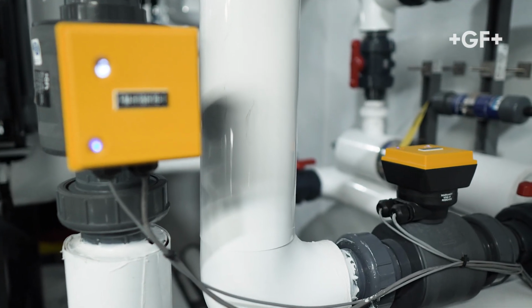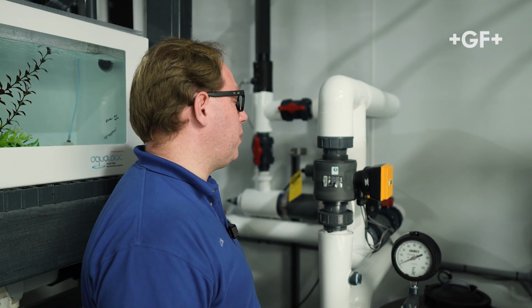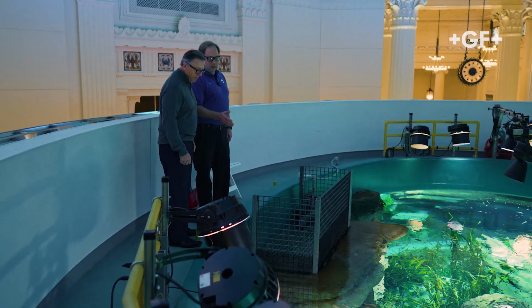Yes, I see there's 90-degree elbows all around these installation points. It can be difficult for an insertion style flow sensor. With the full bore mag, you get high degrees of accuracy, even in tight geometries like this. That's right—I think we'd probably have to use about 20% more pipe if we went with the normal insertion flow for an accurate flow reading.